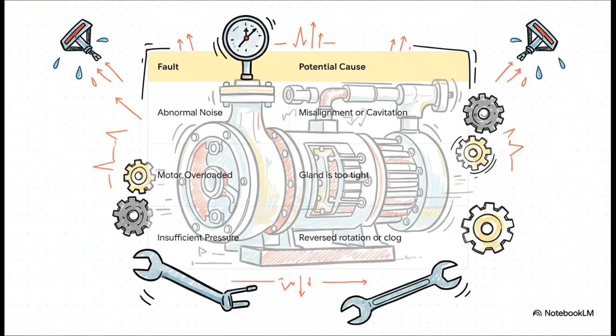This troubleshooting chart right from the manual is so revealing. Hear an abnormal noise? The number one suspect is misalignment, a direct failure of that precision install we talked about. Or it could be cavitation, which happens when the pump isn't getting enough water. Is the motor overloaded? Maybe a packing gland is too tight. See? These aren't random failures.